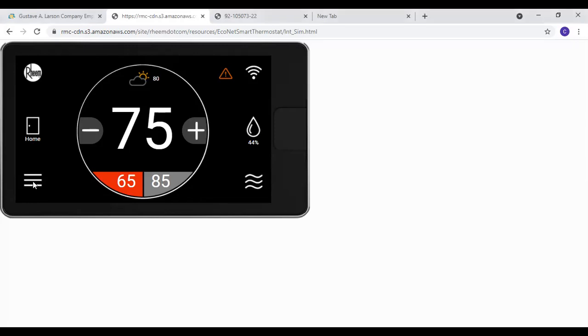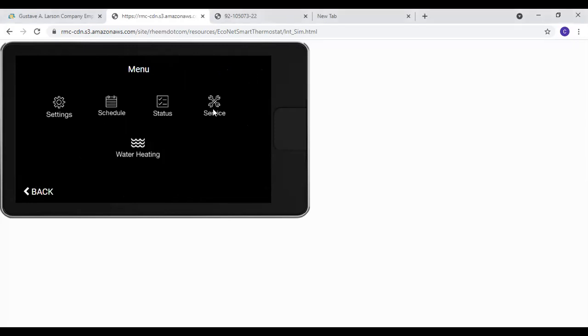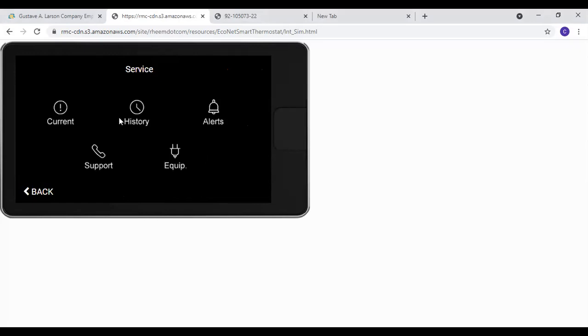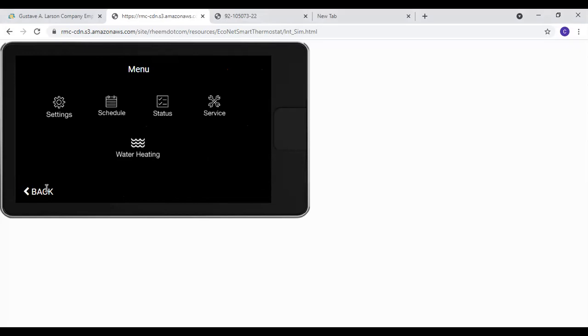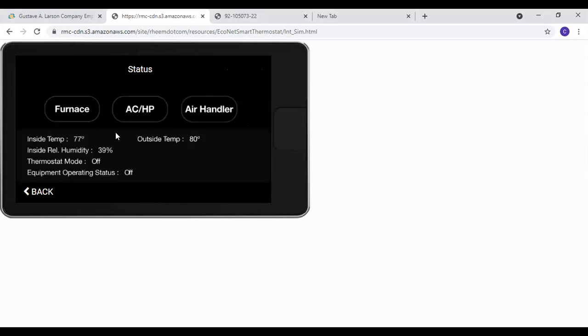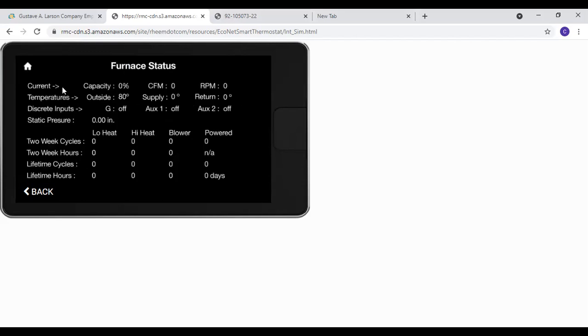So if you go into service, it'll give you any fault history that you have associated with that. And if it does give you specific faults, you want to pay attention to those. If you start seeing a trend of specific faults, you want to hone into that because that's going to tell you what's going on with it. If you go into the status here, this is super, super, super important. If you go into the status of the furnace, down here on the left, it will tell you exactly what your static pressure is.